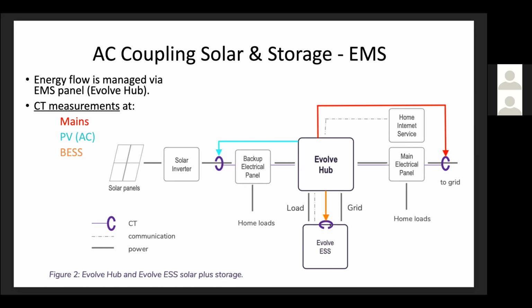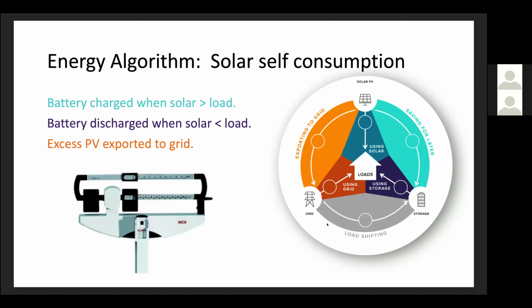And then again, there's a battery CT that will give us feedback on whether or not the battery is doing what we've been telling it to do, to charge and discharge at a certain amount. And we get that battery monitoring information, and all that stuff is nicely displayed on the consumer user interface as well as on the installer user interface. That energy algorithm for solar self-consumption is pretty simple. The battery is told to charge whenever solar is greater than the load, and told to discharge whenever solar is less than the loads. The measurement, decision-making, and command cycle loop is 5 times per second. So it's pretty quick, real-time maintenance of flatline net zero at the meter.